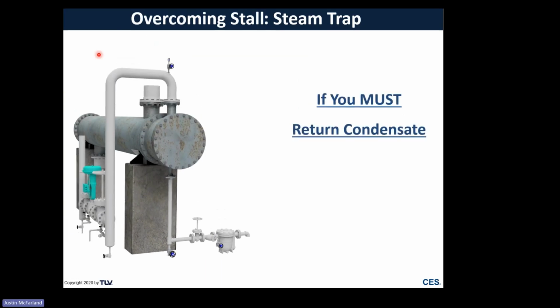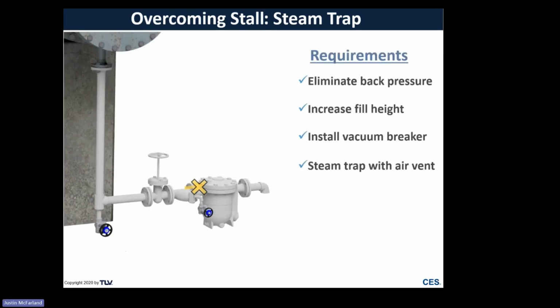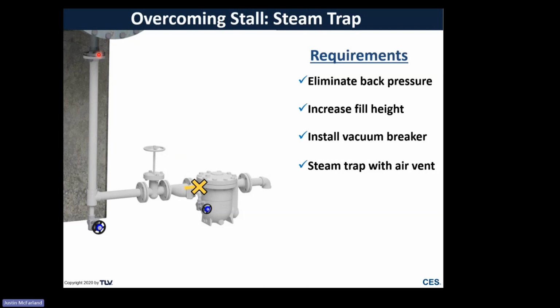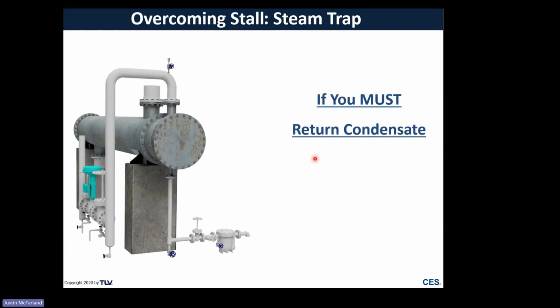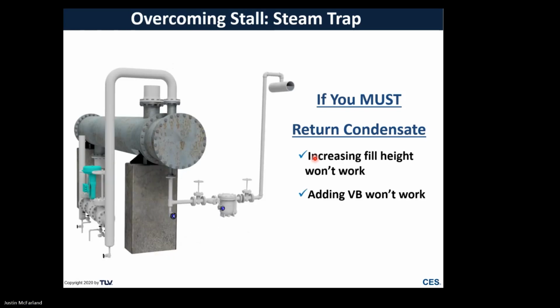So you really need to have all four of those things: eliminate back pressure, increase fill height, install a vacuum breaker, and make sure your trap has an air vent in order to mitigate a stall situation using a trap alone. But as I alluded, if you must return condensate, well, then increasing the fill height's not going to work. Adding a vacuum breaker is not going to work. You're going to have stall still. But there's a solution.